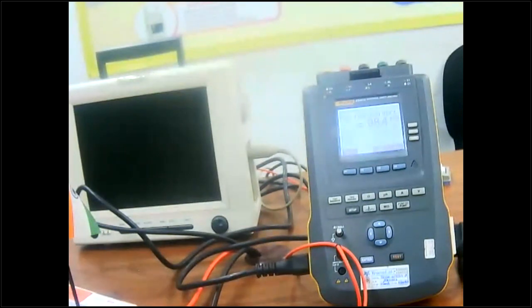So the standard says we use a 10 centimeter square of aluminum foil. You might have to use 2 or 3 layers of aluminum foil, but in a 10 centimeter square, and you are to tape that onto the touchable surface of the patient monitor. Just tape it down, make sure it's in close contact with the medical device, and then you clip your test lead to the aluminum foil.